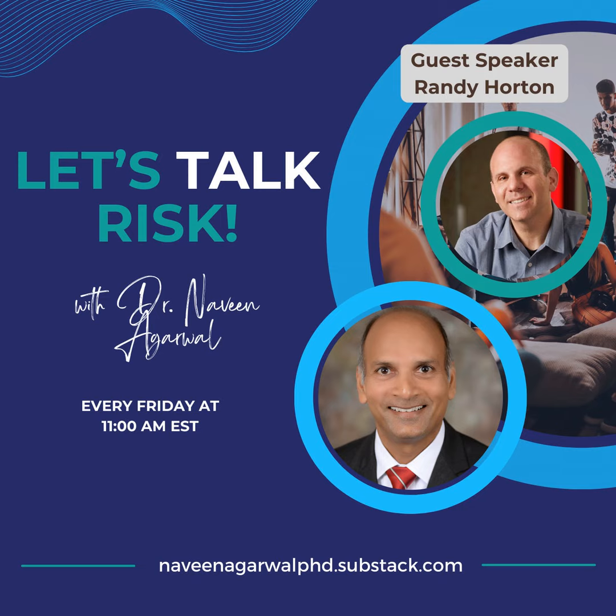Right. So now we have this inherent conflict where medical devices aren't supposed to be updated unless we've run it through the paces and have confirmed that we're okay with it. That could end up resulting, it's all documented. It could be in a letter to file. It could be in a refiling. And instead, we're saying, no, our medical devices, the underpinnings of it, this almost like the cardiopulmonary system of the medical device, is going to be updated nonstop.